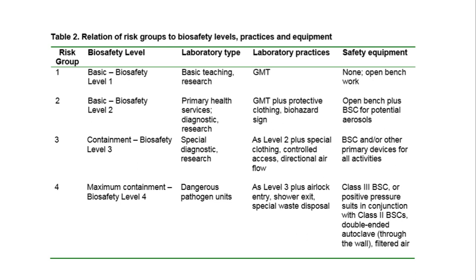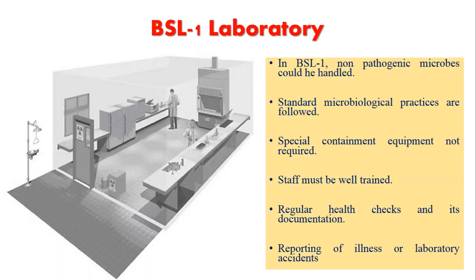BSL-4, also called the maximum containment laboratory, uses all BSL-3 facilities plus airlock entries, shower exits, and special waste disposal. A Class 3 biosafety cabinet — the most advanced type — is used, or a positive pressure suit (like those worn by astronauts) in conjunction with a Class 2 biosafety cabinet. A double-ended autoclave can also be used.